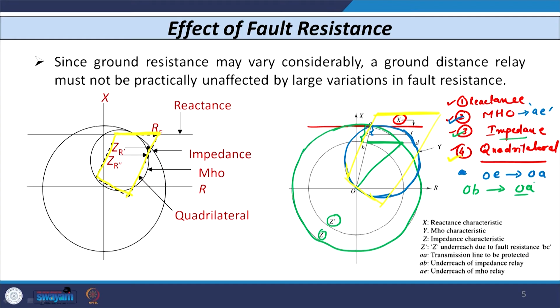So, we have discussed that a reactance relay is not affected by fault resistance. So, basically it is suitable for the protection of a small or short transmission line, because in that case fault resistance is already comparable with line reactance. One more point is that we cannot use a reactance relay for the protection of long EHV and UHV lines, because in case of power swing this relay may maloperate compared to other types of distance relay characteristic. That is why the reactance relay is not used for protection of long lines.